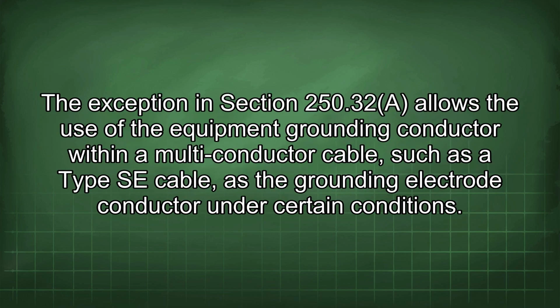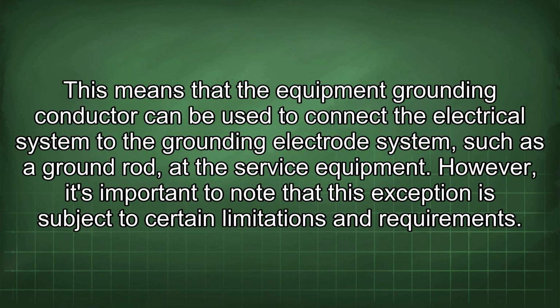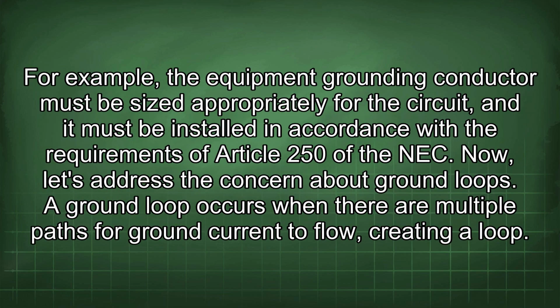The exception in Section 250.32 allows the use of the equipment grounding conductor within a multi-conductor cable, such as a Type SE cable, as the grounding electrode conductor under certain conditions. This means that the equipment grounding conductor can be used to connect the electrical system to the grounding electrode system, such as a ground rod, at the service equipment. However, it's important to note that this exception is subject to certain limitations and requirements. For example, the equipment grounding conductor must be sized appropriately for the circuit, and it must be installed in accordance with the requirements of Article 250 of the NEC.